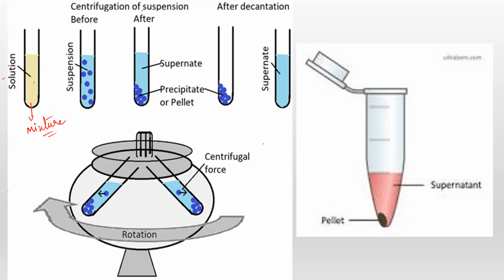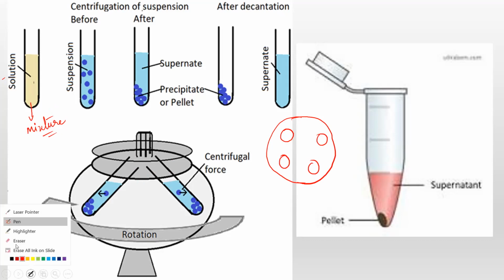Now you must know that a centrifuge rotor, if you look at the top view of the rotor, is like this. So 1, 2, 3, 4. Suppose this can hold only 4 samples. Okay, so there will be many holders, but when you are going to keep the centrifuge tube, always balance the opposite forces. It is like a seesaw.